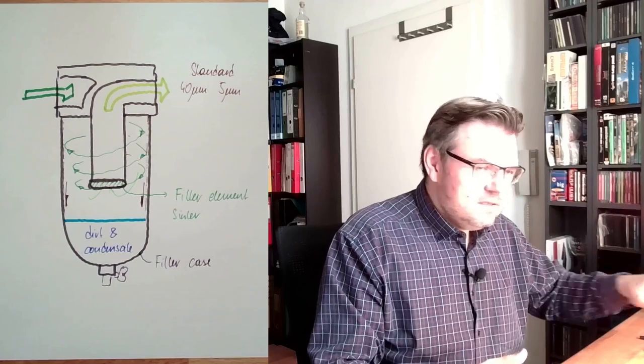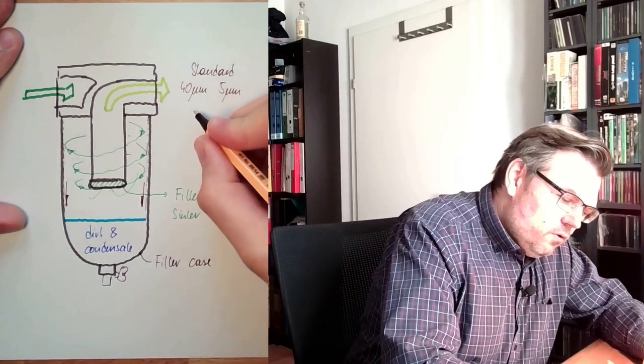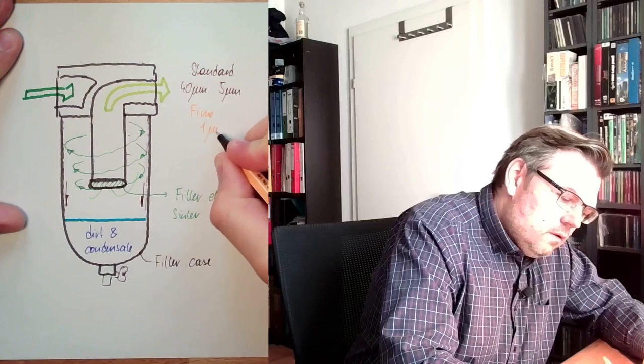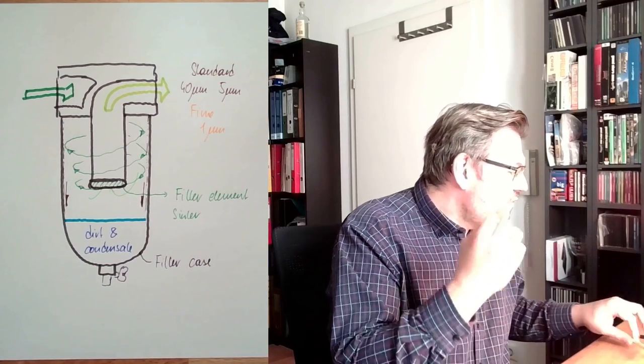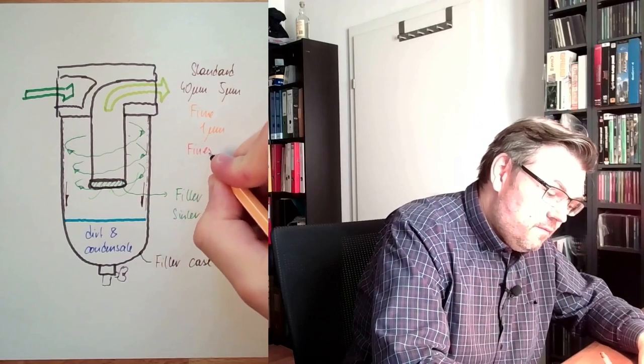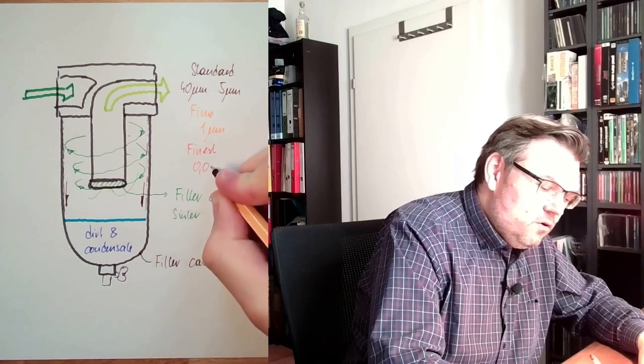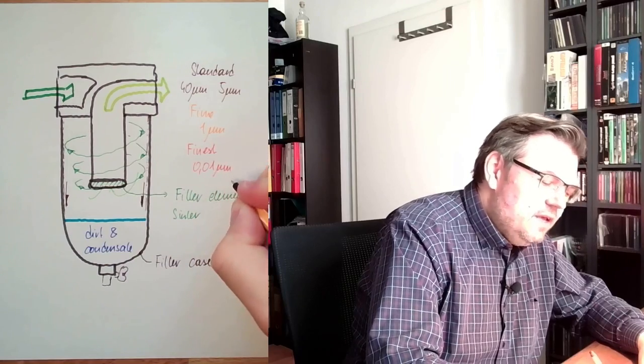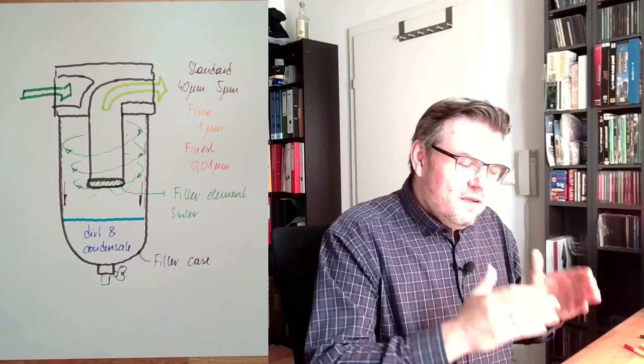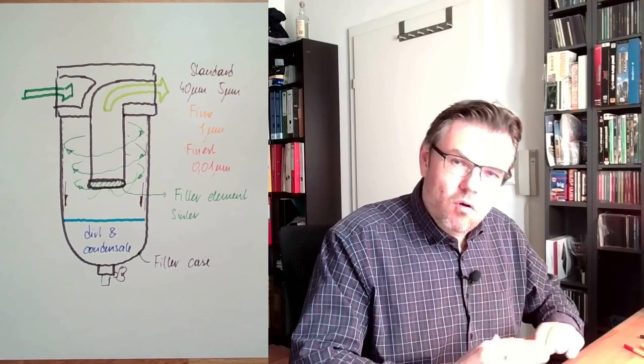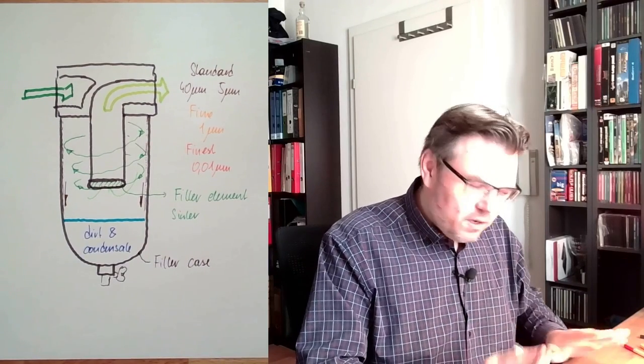Fine filters are down to 1 µm. And the finest filters, 0.01 µm. So this is really clean air then. Filtering really, really clean. In the pharma industry, something like this, really get rid of a lot of oil, essentially all particles inside.